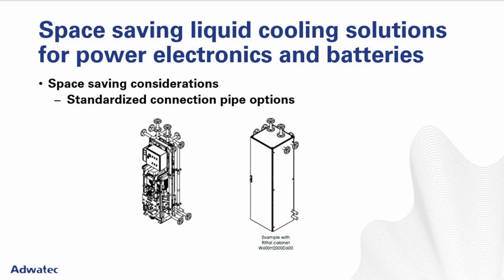So we've gone through this modular structure, we've gone through the slim design, but then there's a third piece to this cooling business, and it's connecting these devices. When we have a cooling unit, it needs to be connected to the technical water side and to the customer's power electronics, and the issue is, of course, how to do the connection pipes.